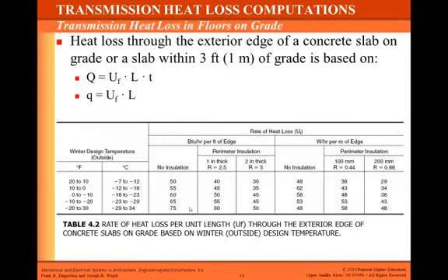So I flip back up here, and they say if you have 1-inch insulation around the perimeter, and your outside design temperature is 14 in Richmond, you would go across here and slide over and you'd have a value of 40. What you're going to do is take that F factor of 40 and multiply it times the length of the room. This is sometimes referred to as an F factor, and it is 40.